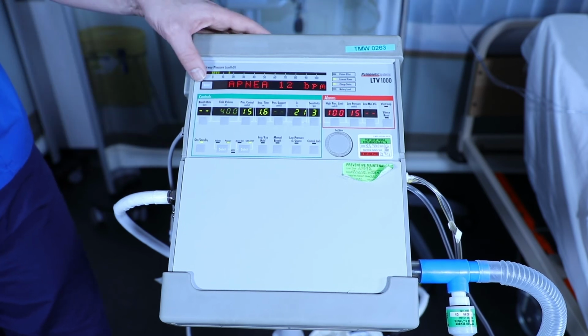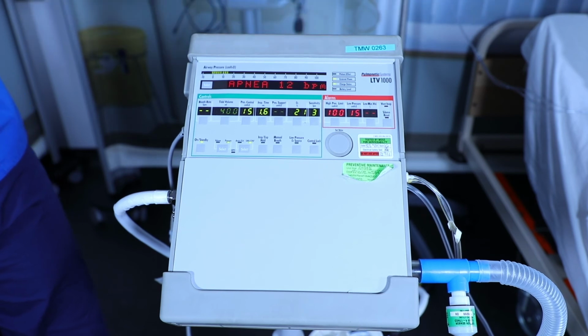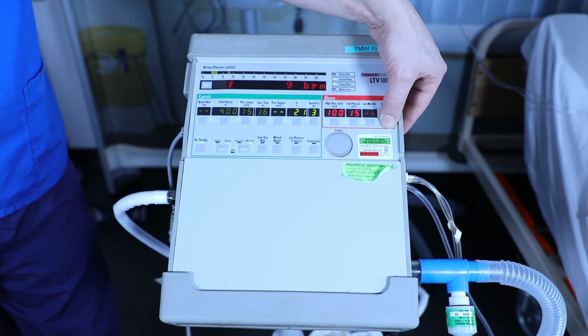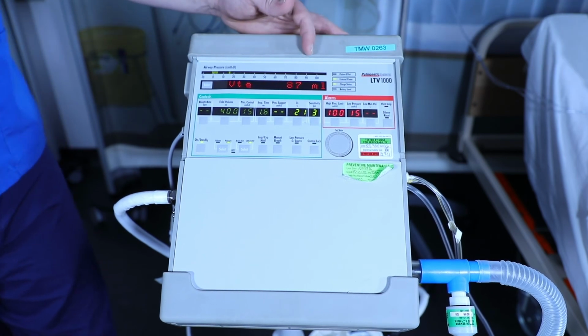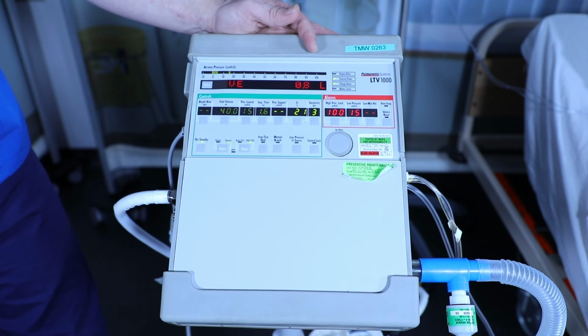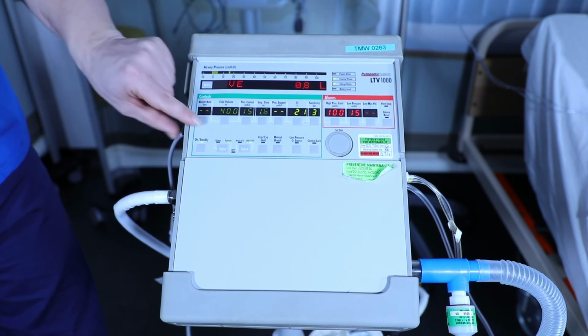So we can clear this alarm in two ways. If the patient was to take 2 consecutive breaths, or using the silence reset button. And this now gives another 20 seconds before the apnea alarm would kick in again. We'll switch the breath rate back on so that this doesn't happen.